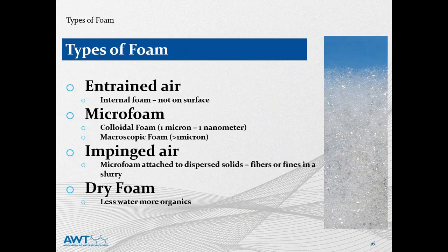There are four main categories of foam. The first is entrained air — taking it back to the stereotypical example, a pint of freshly poured Guinness is a great example; the foam is pronounced and actually in the liquid. Microfoam is simply tiny bubbles. Impinged air is foam created when solids attach themselves to bubbles — in water treatment we actually use impinged air to our advantage in a DAF system, a dissolved air flotation unit, where solids attach to bubbles and float to the top. The last type is dry foam, which is the most difficult to address because there's not a lot of water to disperse it. This is often found in biological systems.